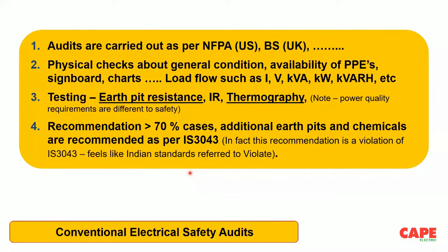So in fact, these chemical earth or these additional earth pits, it's actually a violation of the standard. By looking at the safety audit reports, what we feel is that Indian standards are referred to only to flag violations, whereas all the other standards, as per NFPA, BS, are mentioned in the standard. The client most of the time doesn't know what the NFPA or the BS standard says. Actually, these high-sounding names like NFPA and BS are big names so that people are convinced easily. That is actually not necessary.